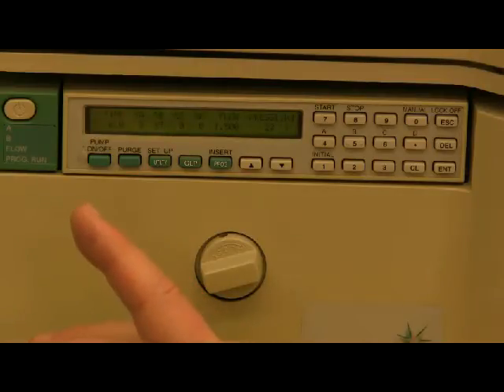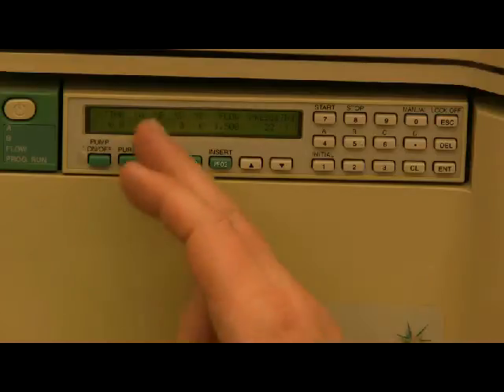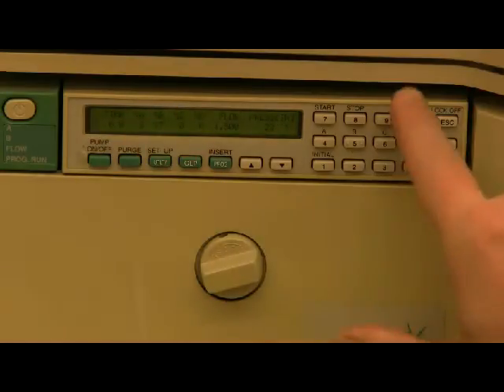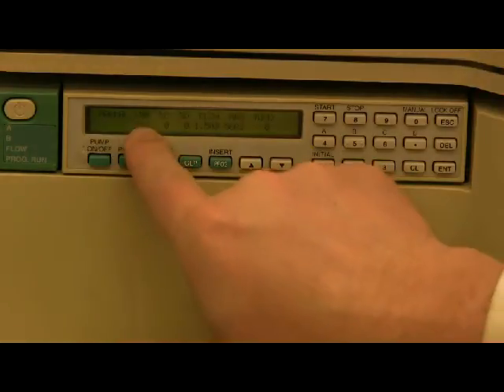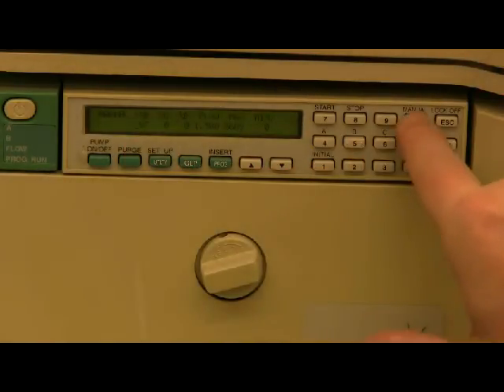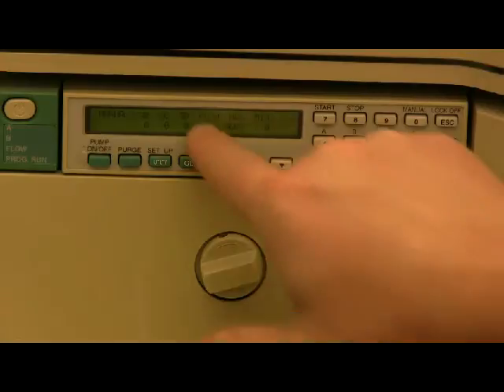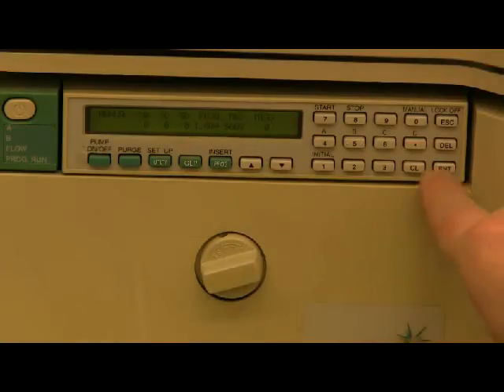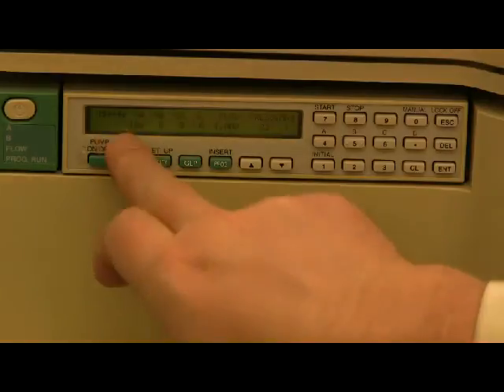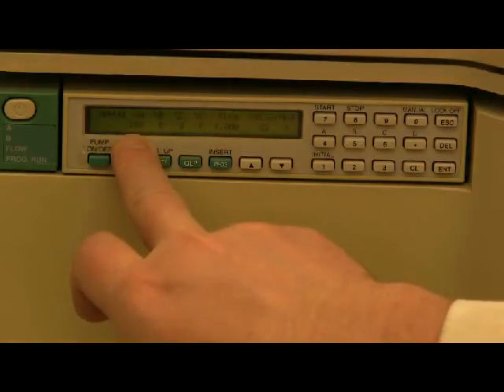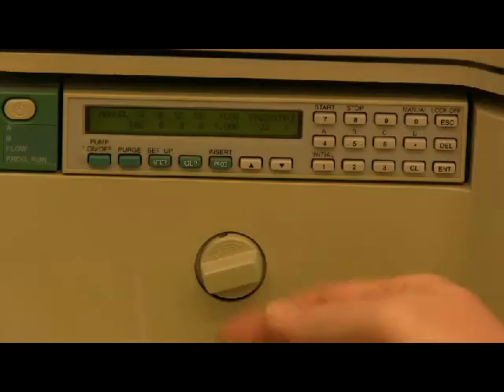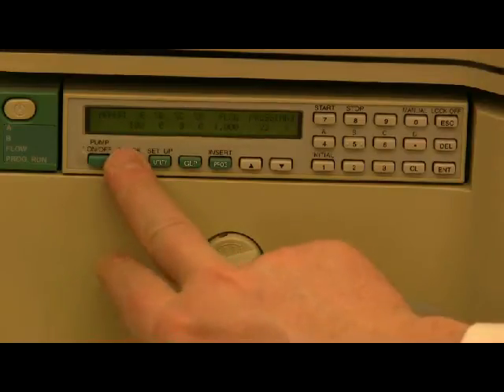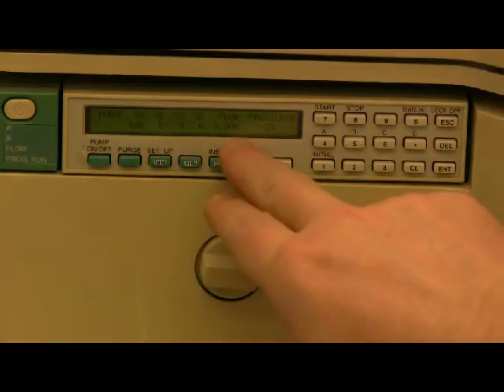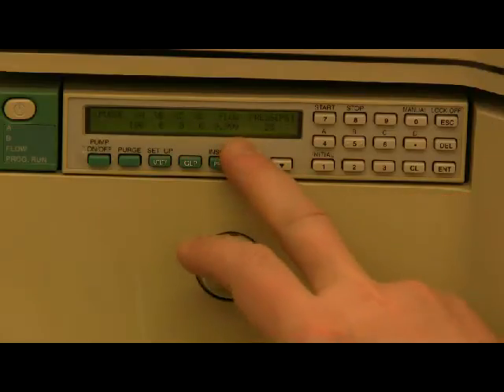To change which line is pumping, you have to hit manual, and then choose B as zero, enter, C as zero, enter, enter, and then we can change our flow rate to 1 milliliter a minute, enter, enter, enter. Now you can see that we're running 100% A. Next thing you do is you hit the purge button. This jumps the flow up to 10 milliliters a minute.